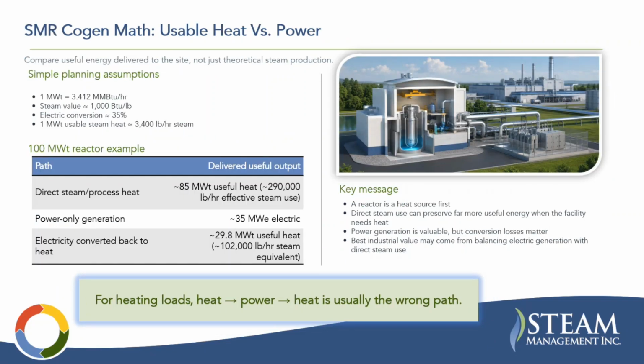Some math here of why I think it's interesting for industry. For a 100 megawatt reactor example, let's say your conversion to steam and your distribution system are 85% efficient. That means you're getting 85 megawatts thermal of useful heat out of it. If you go to power generation, you're getting 35 megawatts of electrical energy. And then if you were to go to power generation and then convert that back to heat for a bunch of satellite electric heaters or users, now you're taking that 35 and multiplying it back by 85%, say, and only getting 29.8. So the best application, it could be argued for these, is a heating load. And like I mentioned with the coal boilers earlier, generating heat and keeping it as heat is more efficient than going to heat and then power and then back to heat.